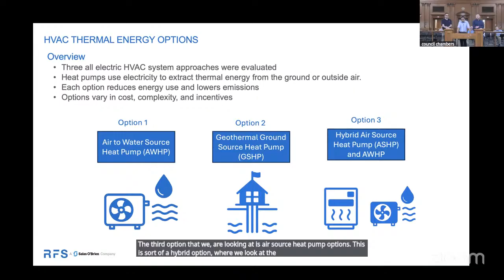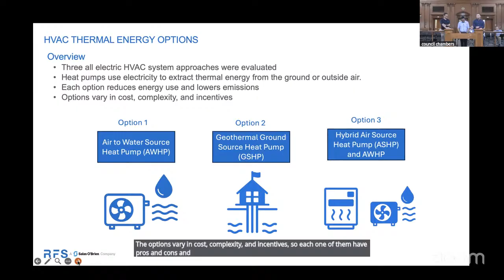The option two that we've studied is the ground source, also called geothermal, option, where the source of energy is essentially the earth. The heat sink is used to take the heat out of the building in summer months and put it into the earth, and then draw it back in winter months to heat the building. The third option that we are looking at is the air source heat pump option. This is sort of a hybrid option where we look at VRF systems combined with an air-to-water source heat pump for reheat. I'll get into that in a little more detail shortly. Each of these options reduces energy use and also lowers emissions. The options vary in cost, complexity, and incentives, so each one of them has pros and cons in what it brings to the table.